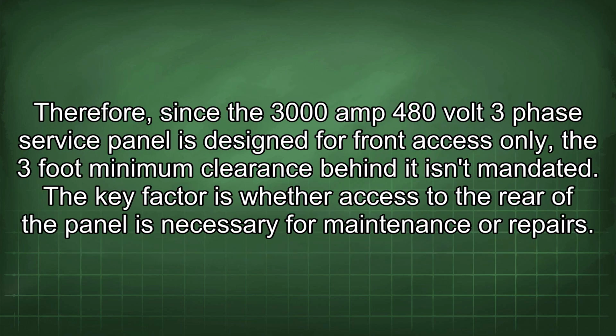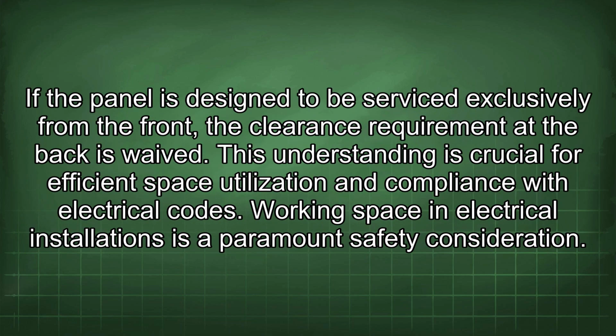Therefore, since the 3000 amp 480 volt 3-phase service panel is designed for front access only, the 3-foot minimum clearance behind it isn't mandated. The key factor is whether access to the rear of the panel is necessary for maintenance or repairs. If the panel is designed to be serviced exclusively from the front, the clearance requirement at the back is waived. This understanding is crucial for efficient space utilization and compliance with electrical code.